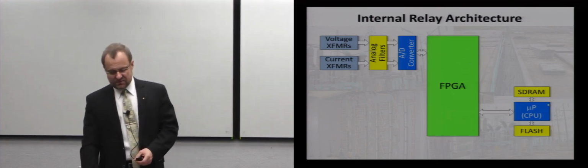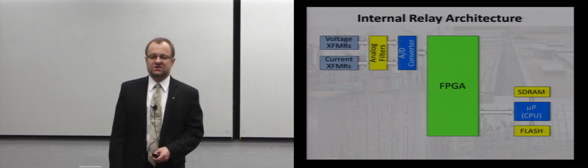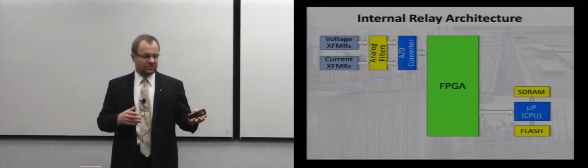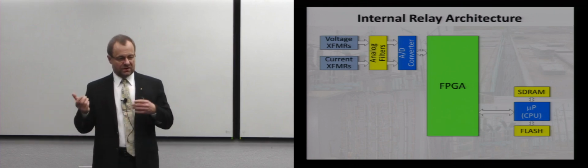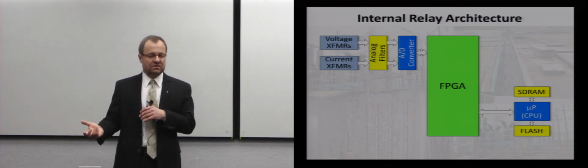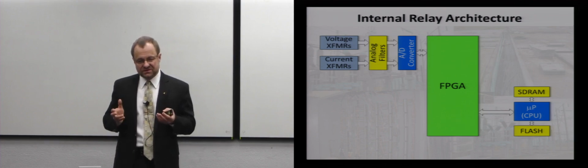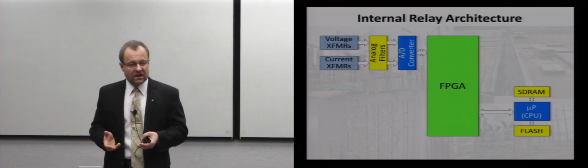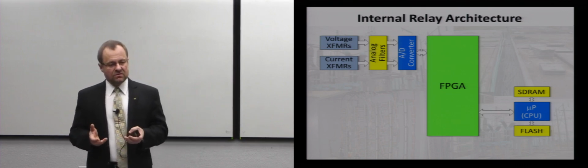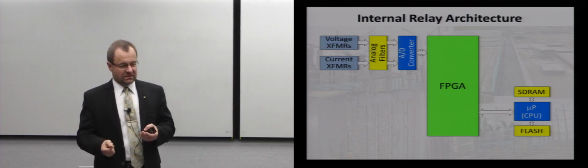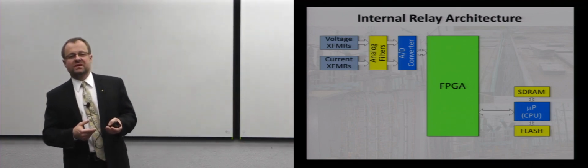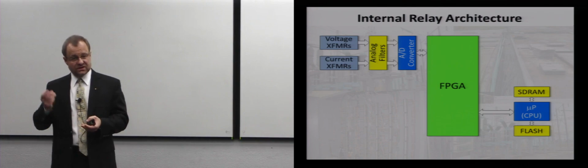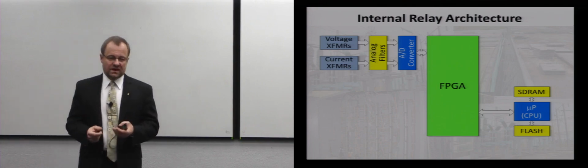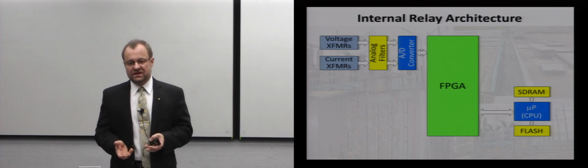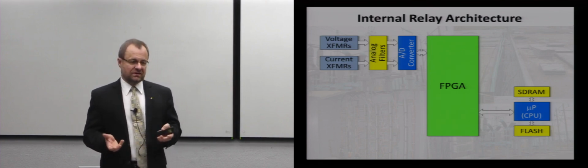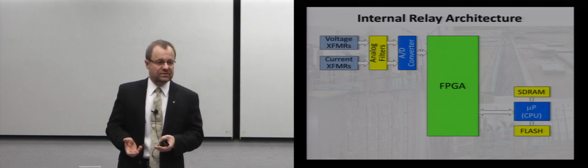What we do, and many other manufacturers do too, is we put a giant FPGA in between. And the reason for that is to move the data quickly from one place to another, from one memory location or one microprocessor to another, and also lift up and pick up some of the very intensive calculations that we have to do. You have to remember that we want to trip very fast. This is not that we will take a sample and we will take 5 minutes to figure out if there is a fault or not. This thing needs to process things very fast. So if we have to put something on the FPGA for the sake of having a calculation done within a couple of tens of microseconds, we will do that, right?